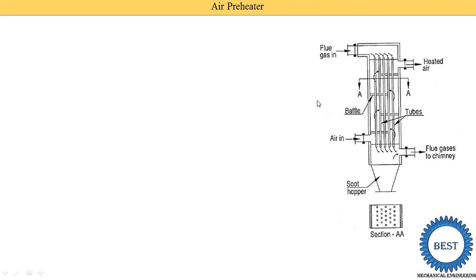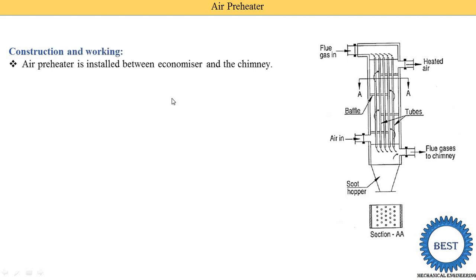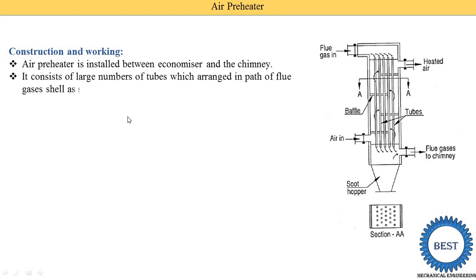Looking at the image of the air preheater, we can see a number of components. The air preheater is installed between the economizer and the chimney, because the exhaust gas from the boiler is first supplied to the superheater, then to the economizer, then to the air preheater, and finally goes to the atmosphere. It consists of a large number of tubes arranged in the path of the flue gases.